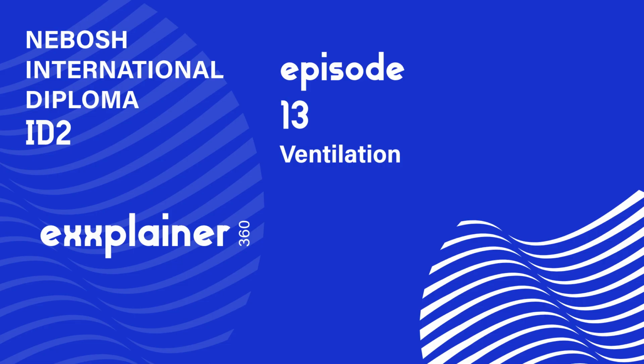Okay, makes sense. Stage 2. This sounds more technical. It is. This is the quantitative assessment. Measurements. Hard numbers. What key things are they measuring? Usually 3 core things. First, face velocity. That's the airspeed right at the opening of the hood. How do they measure that?